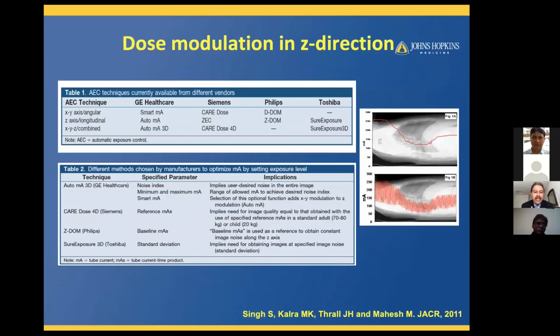And this is the general principle used by the various CT manufacturers, called tube current variation based on spatial variation. However, I want to draw your attention to this: as a medical physicist, it's important for us to understand that the various manufacturers do this modulation slightly differently. They do not do it the same way. And that becomes very important, because if we are helping a clinic to understand the dose modulation, we need to understand how that particular manufacturer employs it.